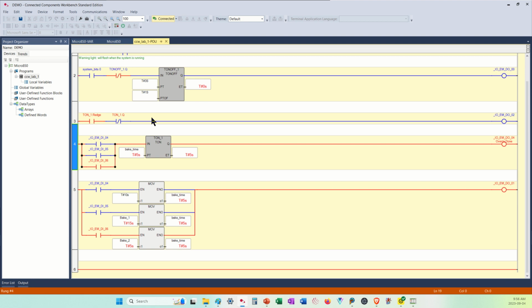And while we're doing this, we don't want the timer to be triggered, left on and running, because an off delay timer, which will be in the next video to show you the difference, will be on instantaneously, and then when you turn it off, it stays on for that off delay period. Okay, so in this case, we're using our internal rising edge bit and the done bit to control an output while the device is being timed.